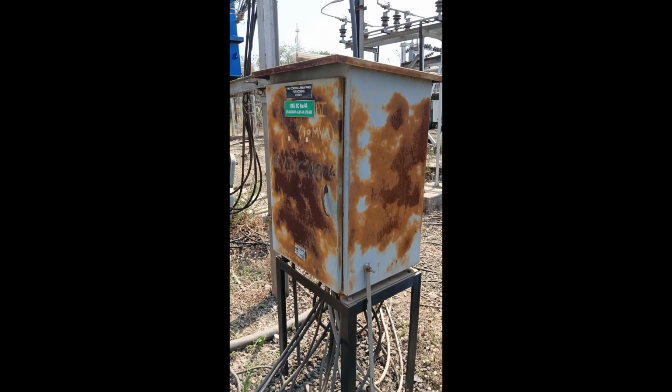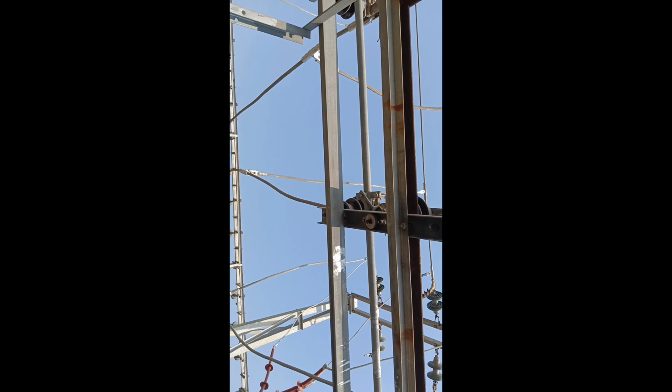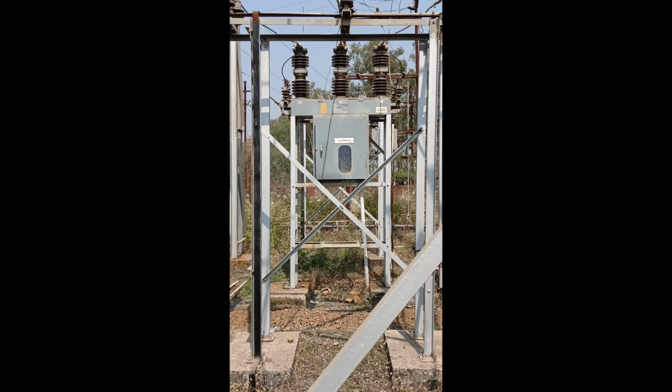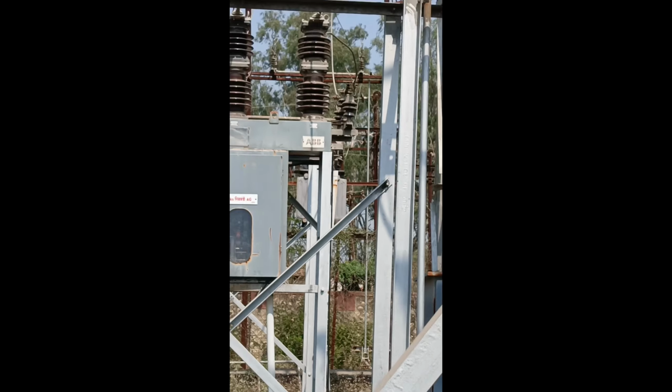This is the incoming feeder control panel which is connected with the control room. This transmission line goes further with the isolator connection, again from the isolator to the next outgoing feeder of the VCB. The isolator is used for the disconnection part for the maintenance of any of the VCB or switch gear. So we manually disconnect the portion and work on the maintenance.